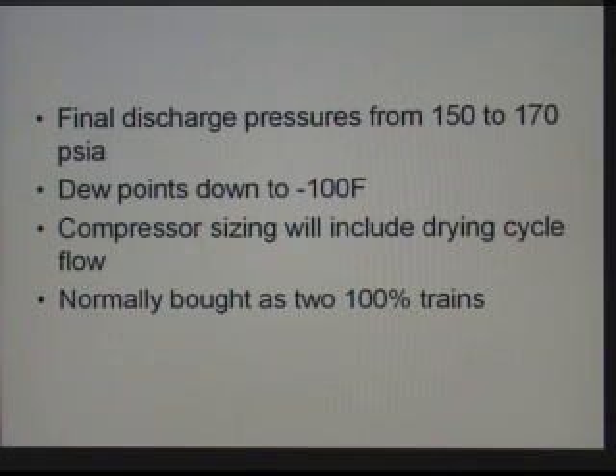I think that they would probably want to have one machine that has maybe 30% more hours than the other, because that way you know which one is going to be requiring maintenance first. And so you can anticipate that. And when it shows signs of maintenance requirements, you can go ahead and swap over, because you've got a pretty long period before that second machine may hit those same number of operational hours and then require that same maintenance.